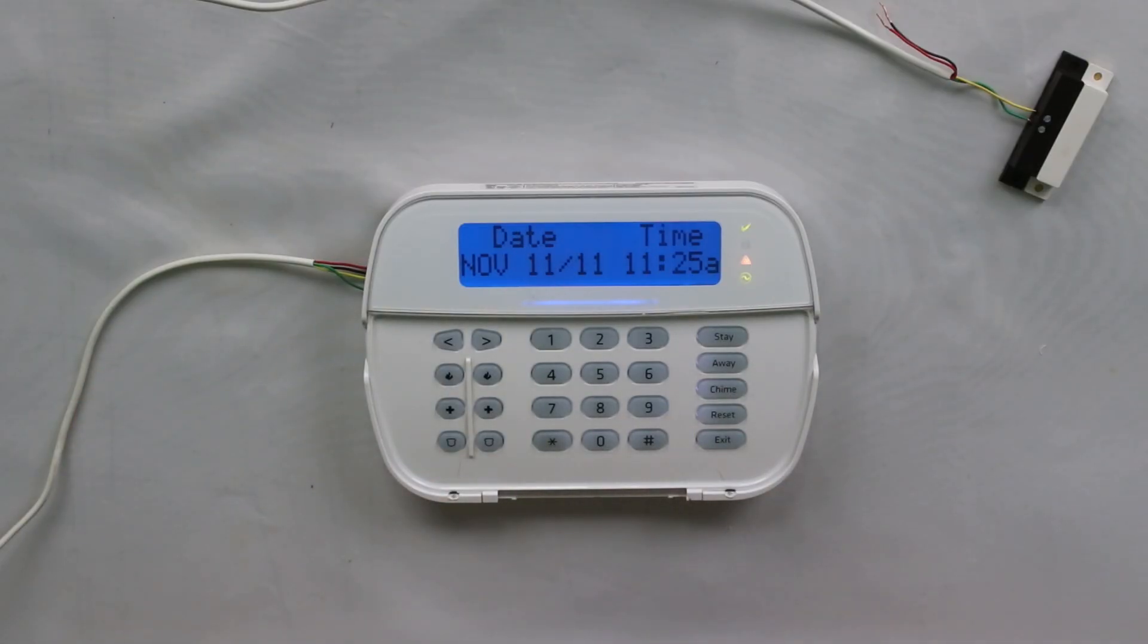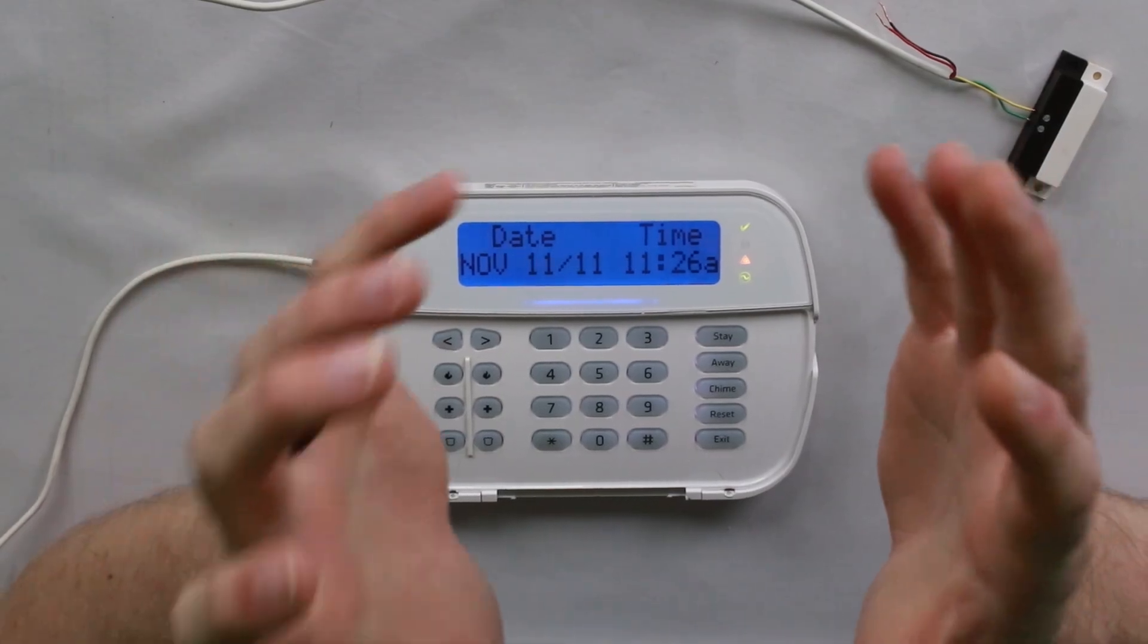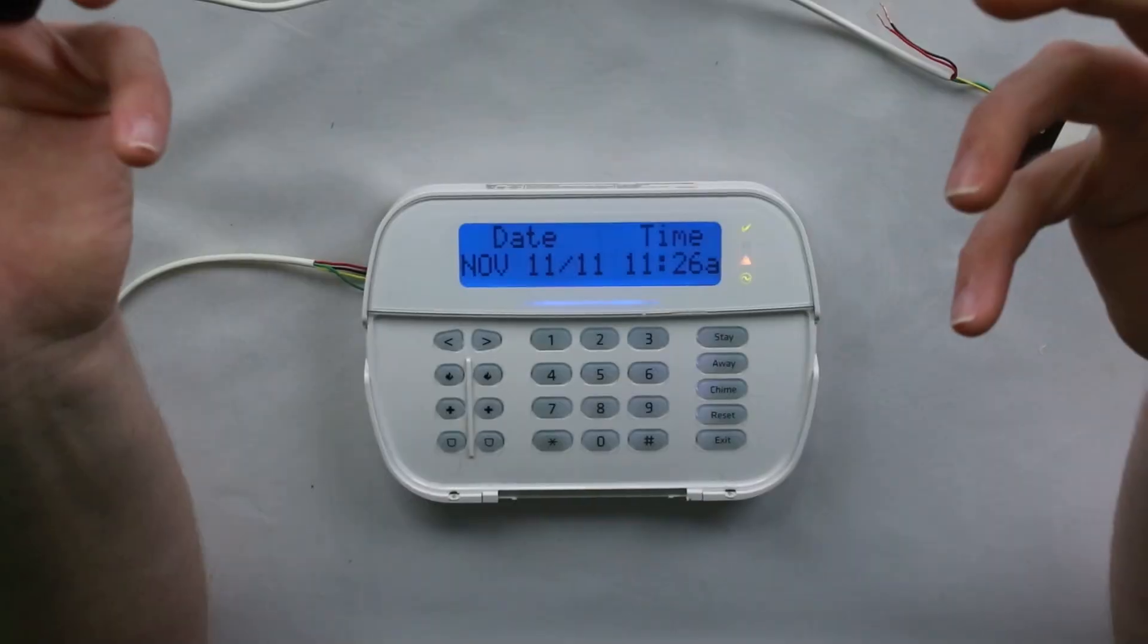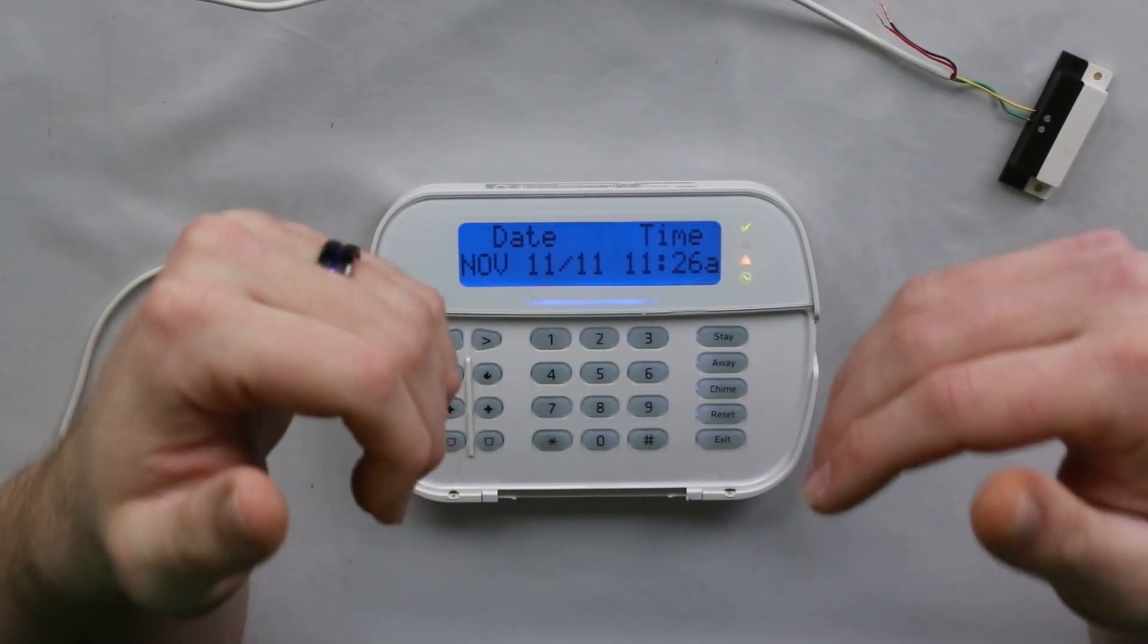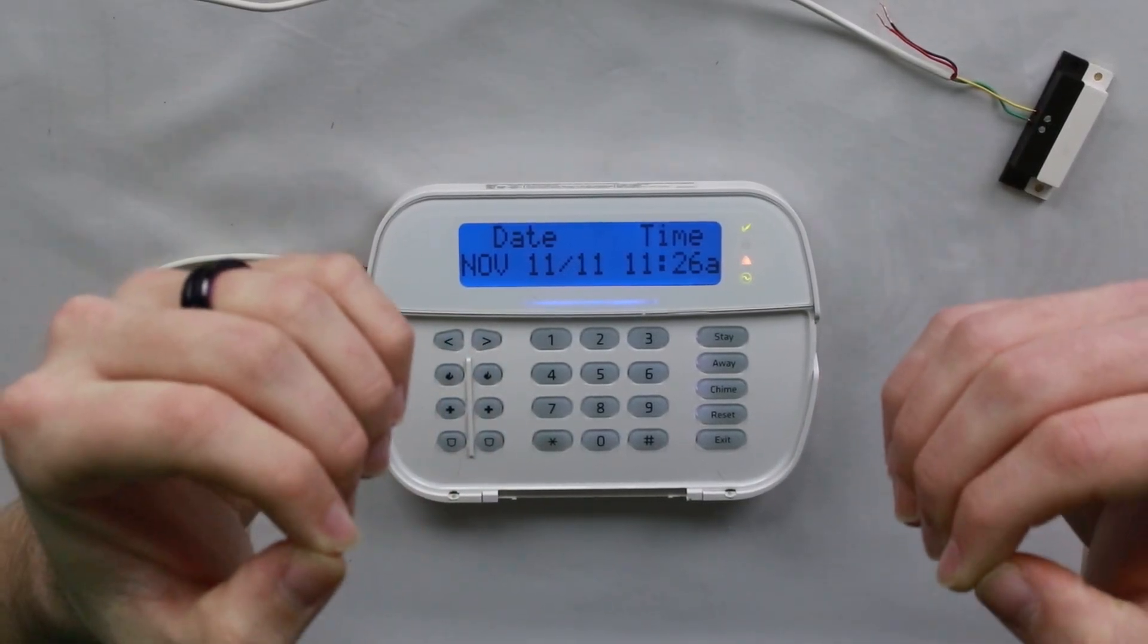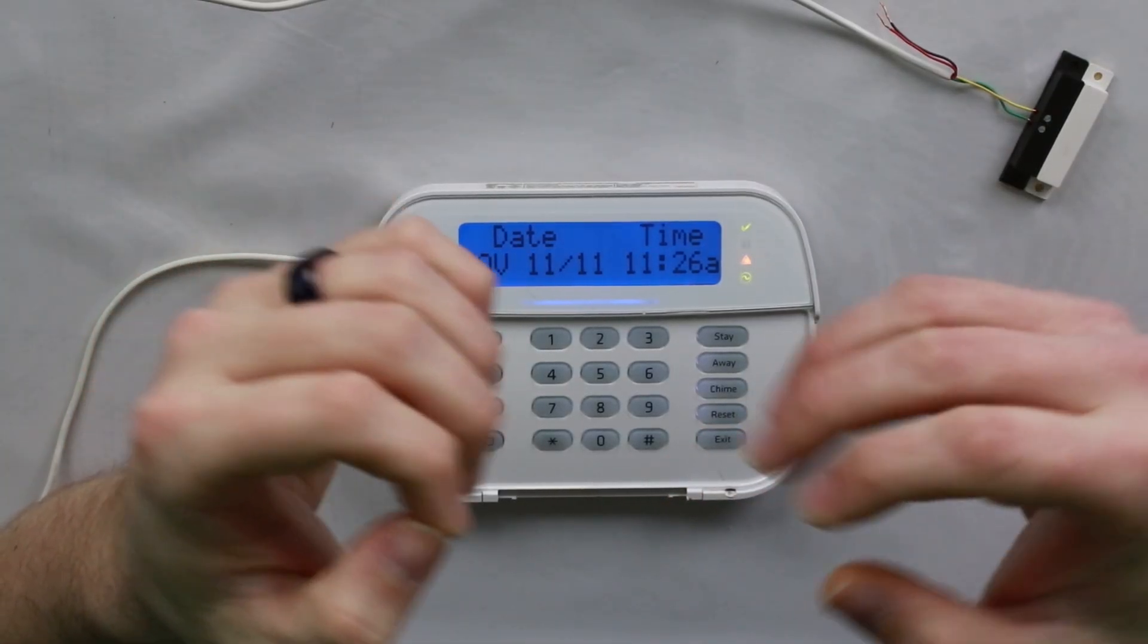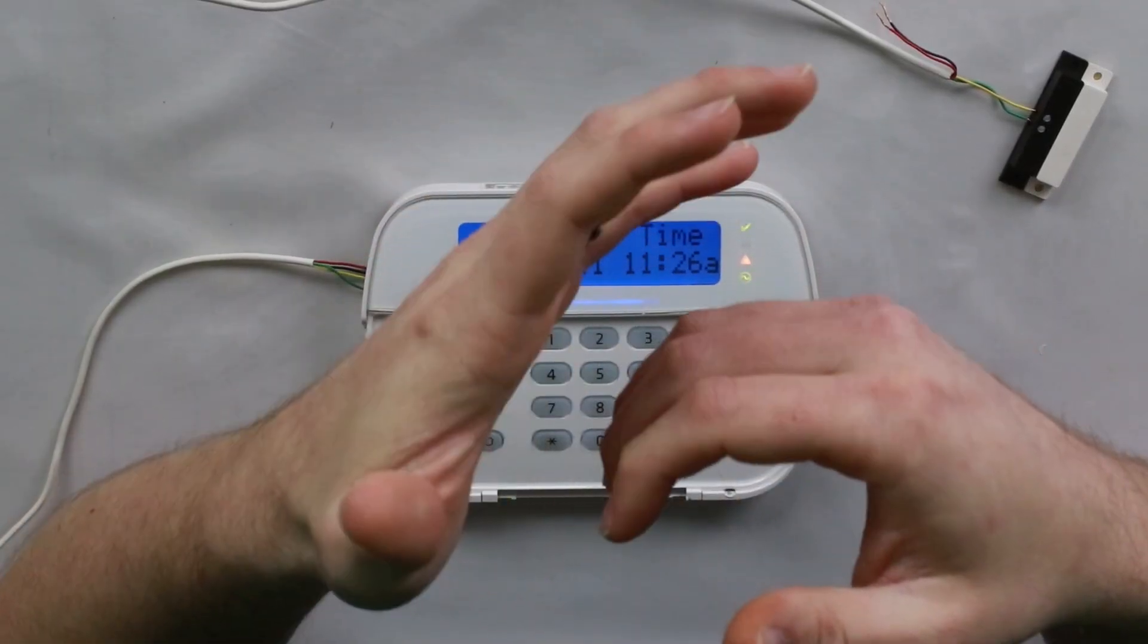The only way to make an FTC clear from a panel on its own is to have your panel successfully send a signal. To do that, essentially, you need to solve whatever is going on with the communicator, phone line, whatever the case may be, and test the system so that it sends out a successful signal. You can, however, temporarily clear the FTC by power cycling the panel. If you do so, just know that if your system still cannot communicate, the FTC will reappear the next time the system tries to send out a signal. So even if you power cycle it, you do still have to troubleshoot and make sure and test whether or not your signals are going to go through.